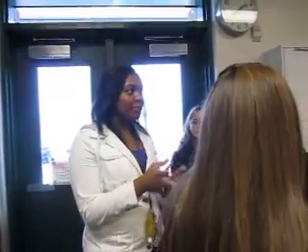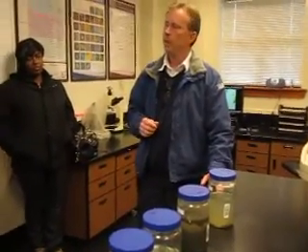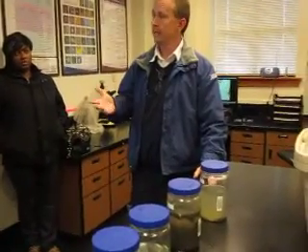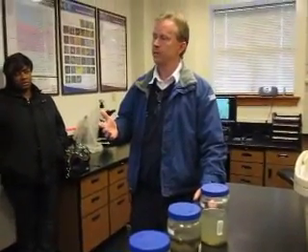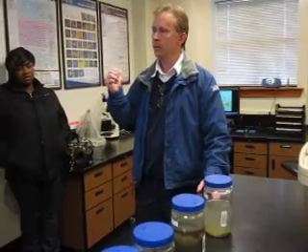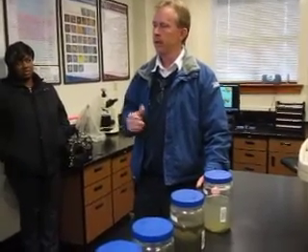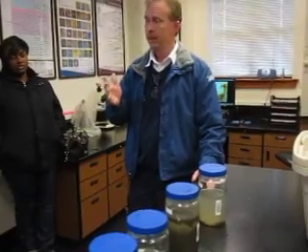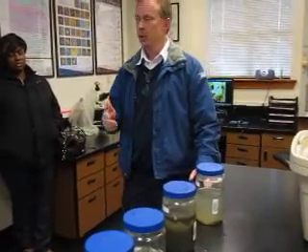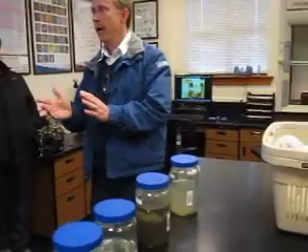Now, go ahead. If it were to be too much food or vice versa, how long does it take to fix it, to get it back balanced? Another good question. If you got too much food, we would increase what we call wasting waste activated sludge. We take some of it out. So it's just a matter of setting an actuated valve to say we're going to waste more out of the system. It's an easy thing to do. We just open that valve a little more and start taking out more.